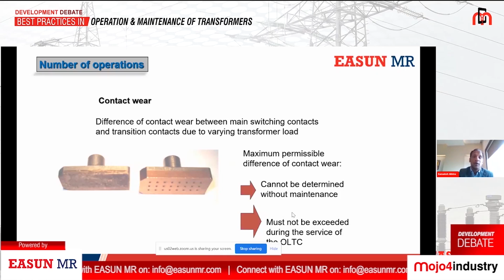In general, if the engineer in the field does not have enough training and knowledge, they will not be aware after how many operations it is supposed to be replaced or maintained. That is the whole thing here. This is where you have to remove, replace and maintain, and you need to know what the contact size is supposed to be and when to replace it. Once a number of operations is completed, you have to change the contacts or maintain them.